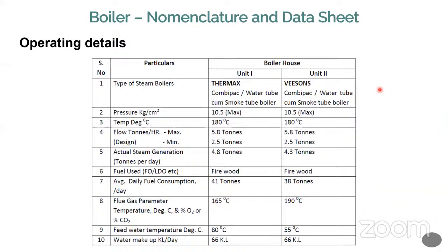So let's assume that I have 2 different boilers. One is a Thermax boiler, the other is a Veesons boiler. Pressure of the boiler is 10.5 kg per centimeter square maximum, at bar. The temperature is 180 degrees. 180 degrees is the steam temperature. Okay. Now the flow tonnage is going to be 5.8 tons maximum, and the minimum is going to be 2.5 tons. So you have to operate between 2.5 ton and 5.8 ton.